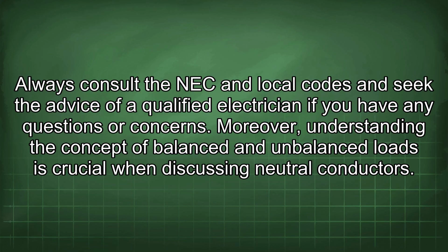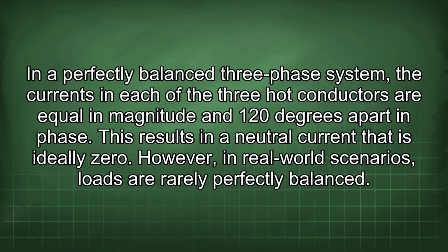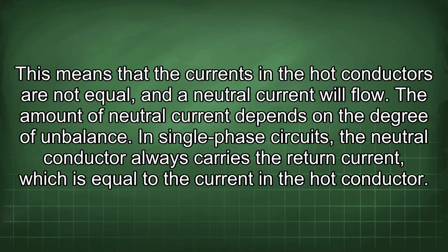Moreover, understanding the concept of balanced and unbalanced loads is crucial when discussing neutral conductors. In a perfectly balanced three-phase system, the currents in each of the three hot conductors are equal in magnitude and 120 degrees apart in phase. This results in a neutral current that is ideally zero. However, in real-world scenarios, loads are rarely perfectly balanced. This means that the currents in the hot conductors are not equal, and a neutral current will flow. The amount of neutral current depends on the degree of unbalance.